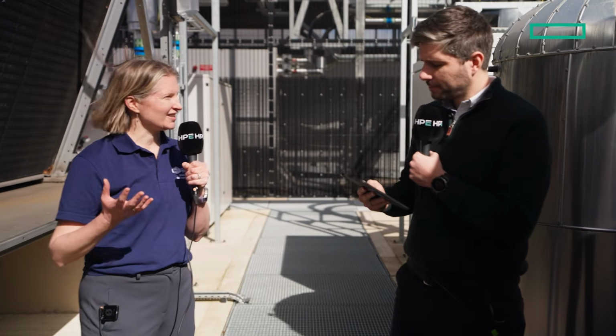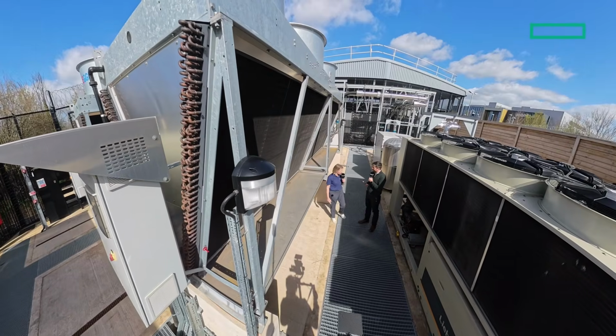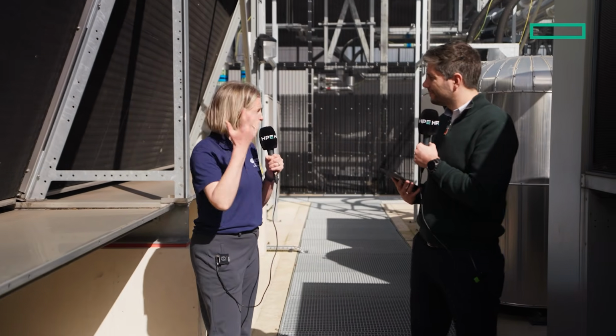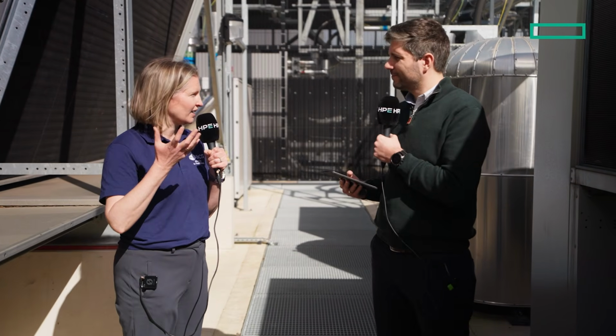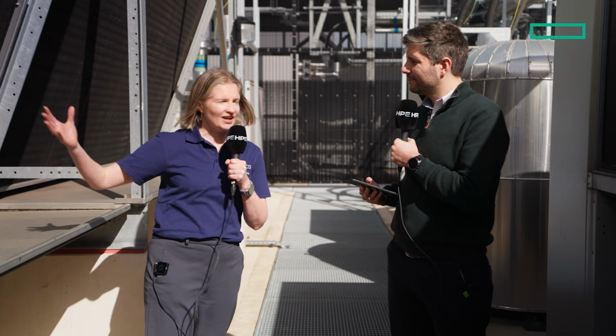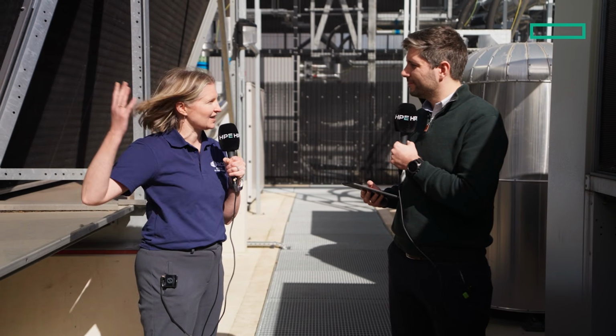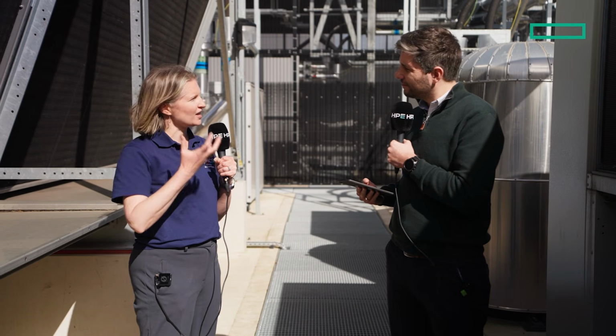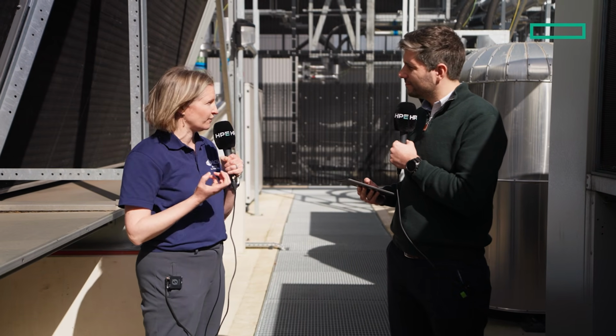On a day like today, with a relatively cool wind and not a particularly hot day, these coolers run in what we call dry mode, so we're not losing any water here - it's a closed loop, and the coolant returns back to the system. If the outside temperature gets a bit hotter, these radiators will start dripping water down the outside of them, which provides a bit of extra cooling through evaporative cooling.